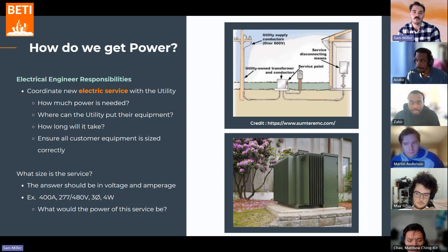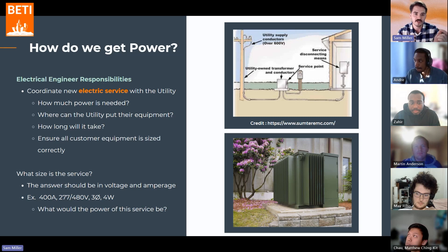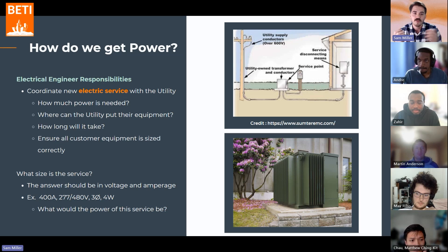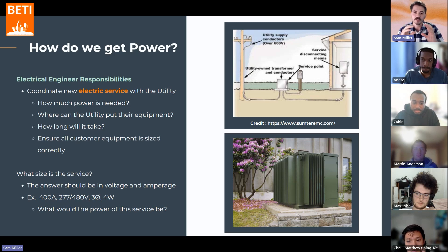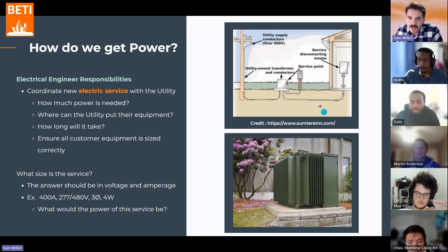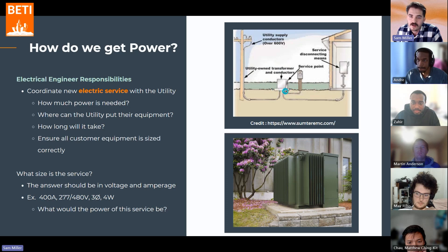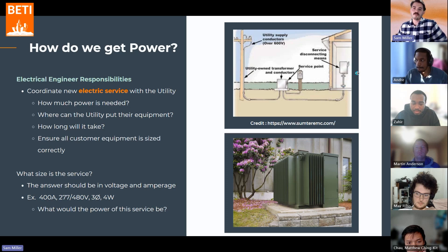It's very important that we coordinate with the utility engineers. I was out on site for a couple of different projects this week, meeting with the power companies, walking around the site saying, here's where we want to put your transformer so that we can pull power from it and into our building. This is the utility-owned transformer — we call it a pad mount transformer because it just sits on a concrete pad, just like it shows there. The utility owns this equipment and we pull our electric service into the building, which then goes into all of our distribution equipment.